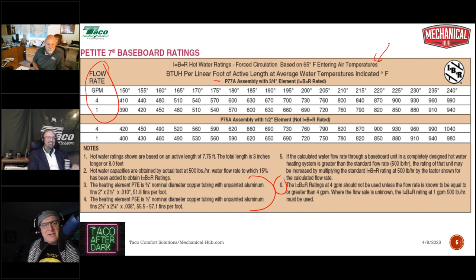Who knows? Number 4 says the heating element P5E is 1/2 inch nominal copper tubing with unpainted aluminum fins, 2 1/4 by 2 1/4 by 0.008 inches, 55.5 to 57.1 fins per foot. What we're learning here is the fins in the 1/2 inch element are bigger, thinner, and there are more of them per foot. Hence, you're going to get slightly more output per foot, 20 BTUs per foot in this case. Not a lot, but it is significant. It's noticeable, let's put it that way.